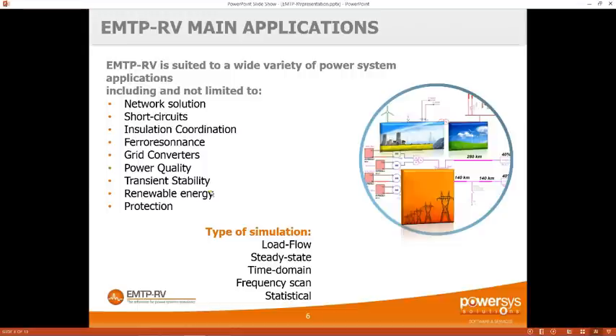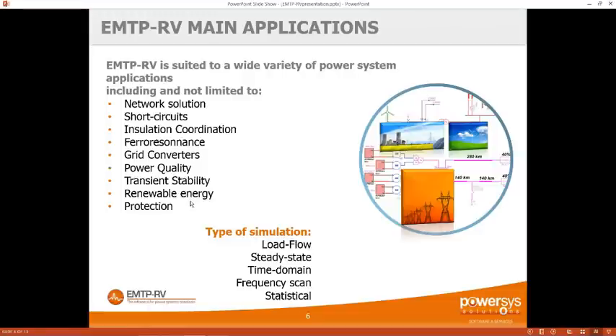We can also do transient stability. For that we have a library of AVR and governor models, and instead of running a simulation of less than a second, you run a few seconds or minutes to study the reaction of the control. Finally, something new being released this year is the protection tool. In EMTP we can reproduce saturation in the CVT, ferroresonance in the CVT, saturation in the CT, and in the relay model we reproduce each step: the burden resistance, the anti-alias filter, the sampling, the DFT to extract the phasor, and all the logic from the manufacturer instruction manual.